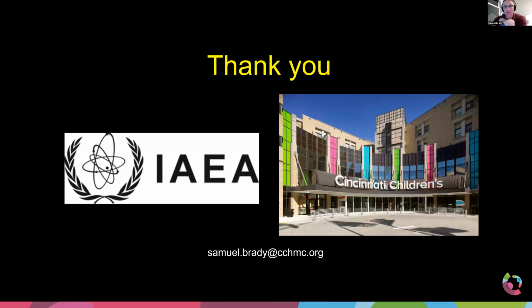And that is a collaborative effort between the medical physicist and the radiologist and technologist. We kind of talked about this teamwork effect a couple of weeks ago, that we all work together. And in this case, it's also probably a very good relationship with the vendor. When you purchase the equipment, you have your field service engineer that will come in and periodically do their periodic maintenance or their PM, not testing, but corrections. If you have a good relationship with them, then you can sit down with them and say, hey, I want the shortest pulse width possible. And they can help you dial it in if possible.